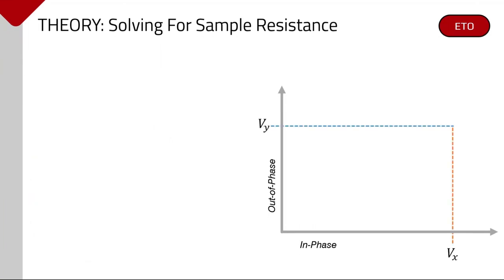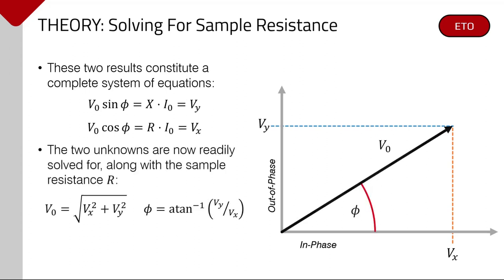Evaluating this demonstrates that we have now solved for V sub Y in terms of the sampling rate delta T and the integration interval T sub M, both of which are known, and the numeric results of the second MAC operation as executed by the ETO firmware. Comparing to our original form of the total measured voltage now yields a complementary expression for the out-of-phase component oscillating at the drive frequency. The in- and out-of-phase components are now defined, so it is trivial to solve the remaining system of equations. Having values for both V0 and phi relates critical diagnostic information about the measurement. It is assumed that the sample circuit comprises purely a resistive element, so the presence of a significant phase angle, indicating an appreciable reactance component of the impedance, is often worth investigating further.